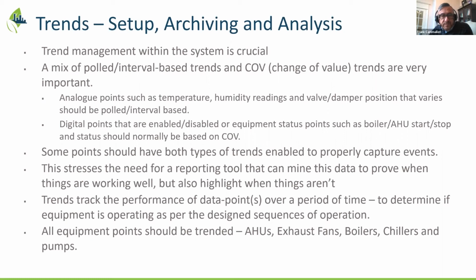So a little bit about trends for those not familiar with the different types that exist. Basically there's a mix of them. There are interval-based trends, such as analog points like temperature and humidity, polled every 5, 10, or 15 minutes. 15 minutes seems to be the standard, and it's important that when they get set up with that interval in place, you don't want anything less than or more than that. If you have hourly readings, you don't get the granularity you need, and sometimes you even need 5-minute intervals. That's what we mean by analog.